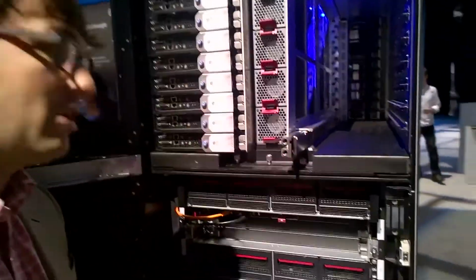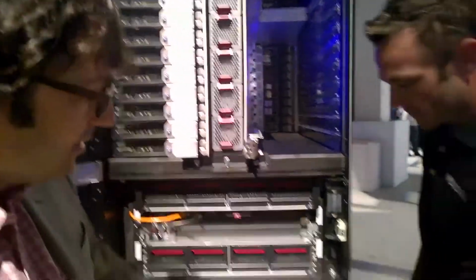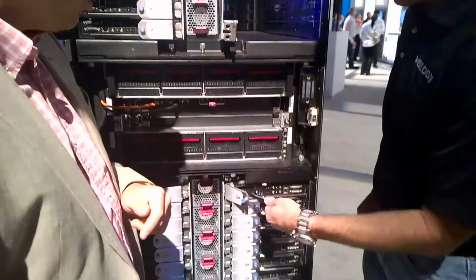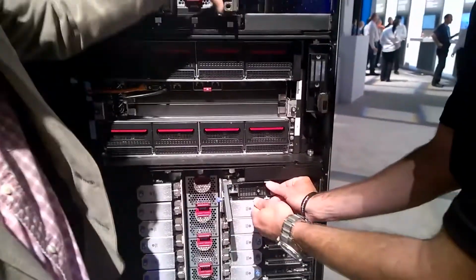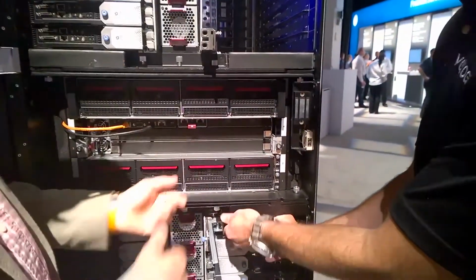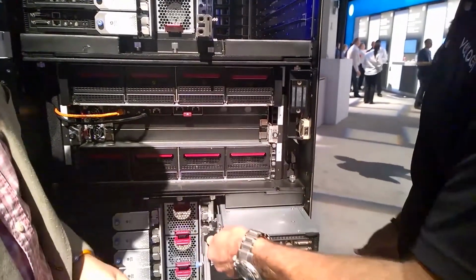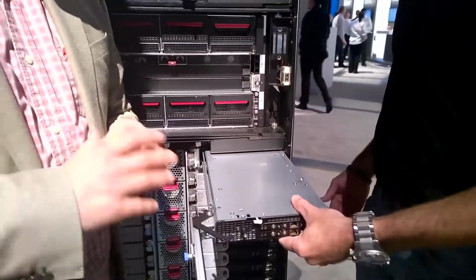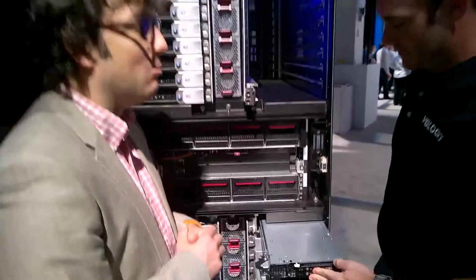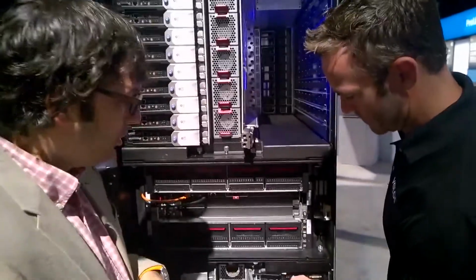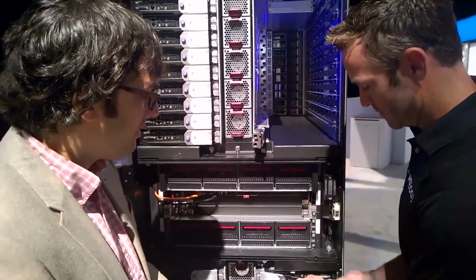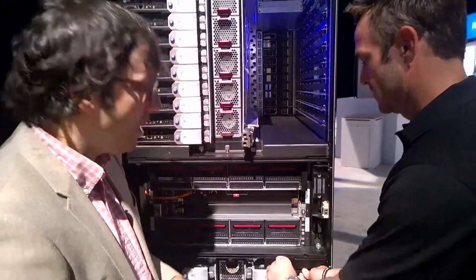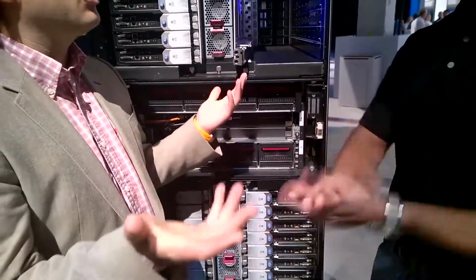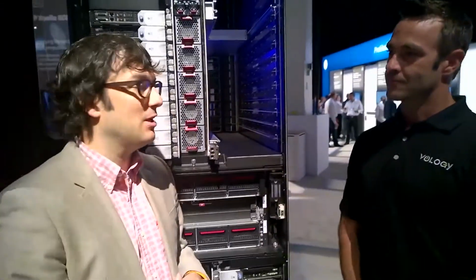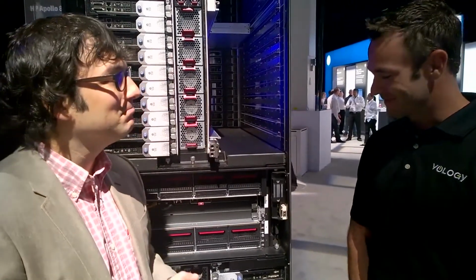So let's do servicing of a node. Basically all you do is first disengage the cooling system. As you do that, the thermal bus bar moves in, then disengage the electronics, pull the tray out, and you're done. You didn't break any water connection, there's no leak. You re-engage, put it in, electronics back in, engage the thermal bus bar, you're done. Servicing a liquid cooled node is as easy as servicing an air cooled one.